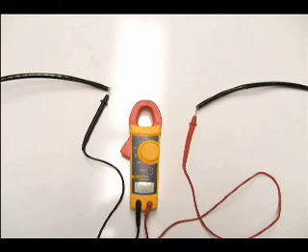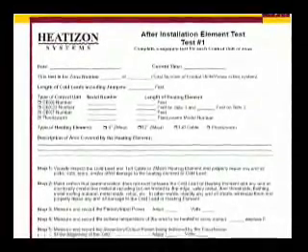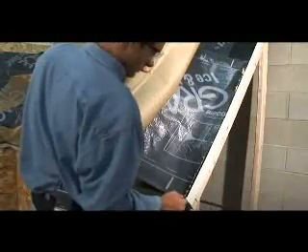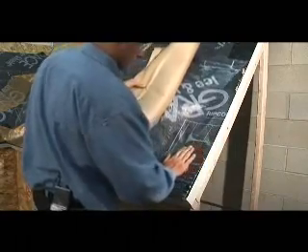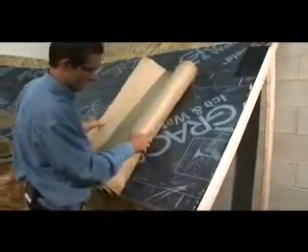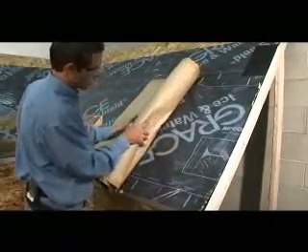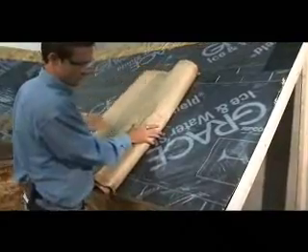With the system free of any shorts, complete the after-element installation test, which can be found in the Heatizon Installation Manual. Fill out the after-element installation test form completely. After performing all the system tests and verifying that no shorts exist, cover the Z-Mesh with a layer of ice and water shield. Ice and water shield or EPDM must be installed over Z-Mesh, and if desired, may be installed under Z-Mesh as well.